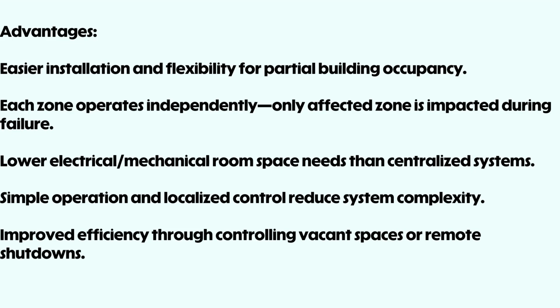Some major advantages include independent operation. Each zone functions separately, so one malfunction doesn't affect others. Lower installation cost and minimal mechanical room space. Pre-tested certified performance by manufacturers. Fast commissioning and easy scalability. Improved control for unoccupied zones, allowing energy savings during off hours. Flexible equipment options from multiple vendors.